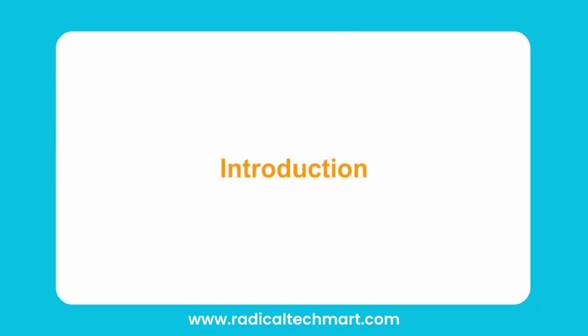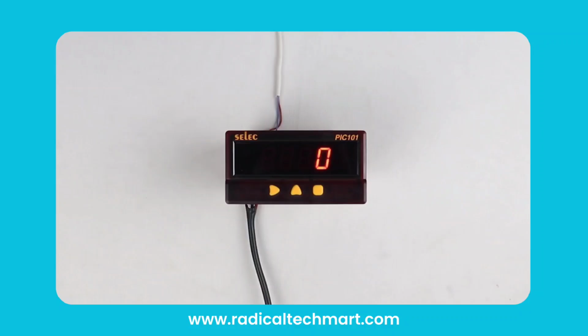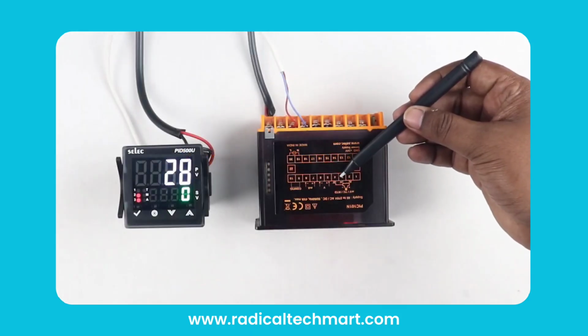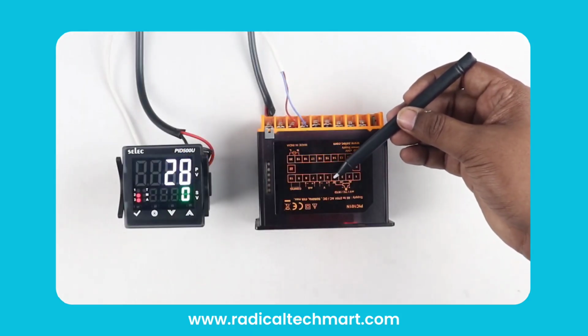Hello everyone. Today we will learn about terminal connection and programming in the PIC101 unit. First, let's look at the terminal connections. Terminals 2 and 3 are for your TC input. Terminal 4 is for your RTD input.